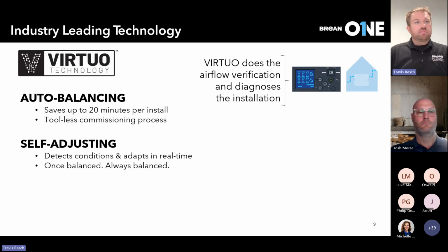The next is self-adjusting. We're monitoring a number of variables within the product itself twice a second. So if we have a restriction for whatever reason, filter, termination, ductwork, etc., the unit's going to detect those conditions and adapt in real time. So once that unit is balanced, it's always going to stay balanced. If we run into a situation where we get complete blockage for whatever reason, we're going to detect that.